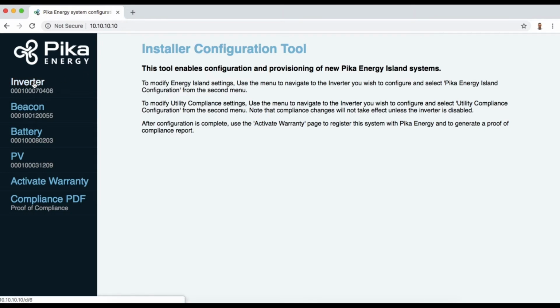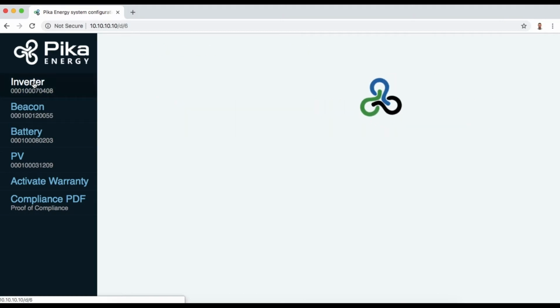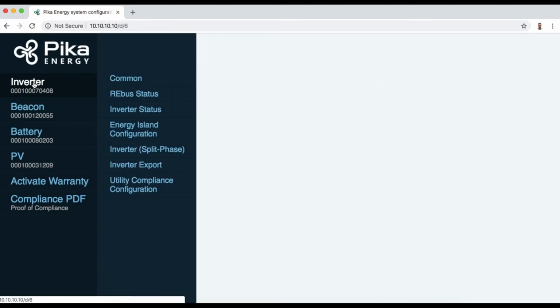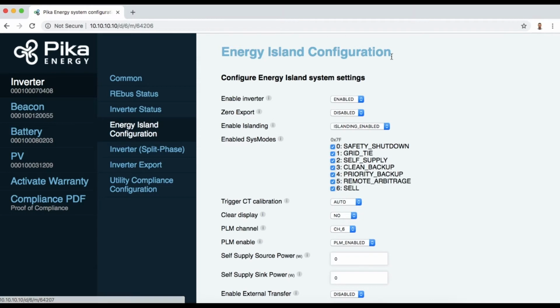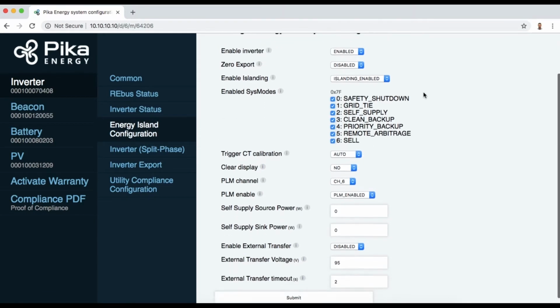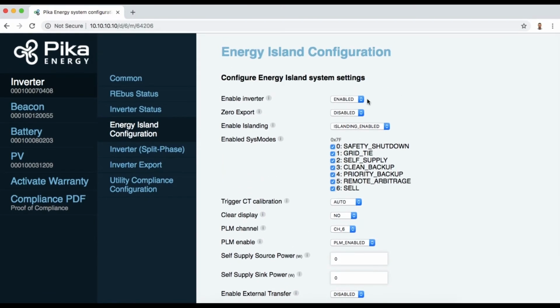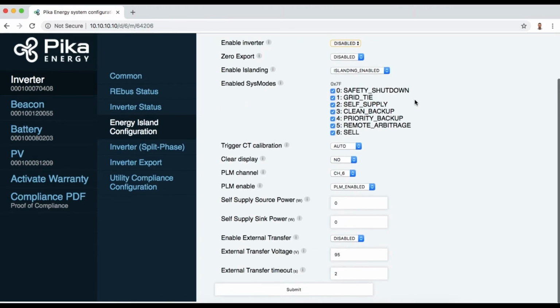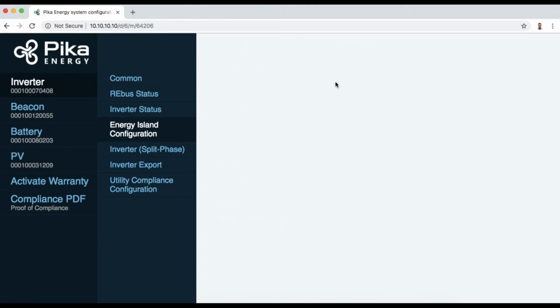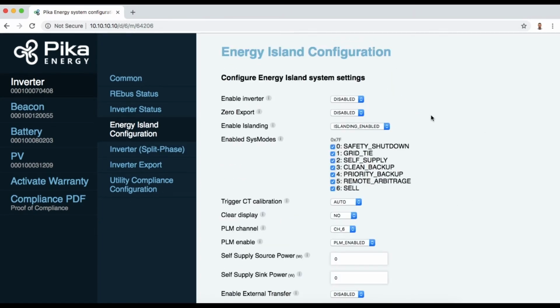So the first thing that I'm going to show you is how we configure the inverter. So if you click on the inverter screen, as I just have, and then you click on Energy Island Configuration, you'll see here that you have a number of options of things that you can configure and change. In order to make any changes, you have to have the inverter disabled, and from there you will submit, and at this time I can make any changes as needed.